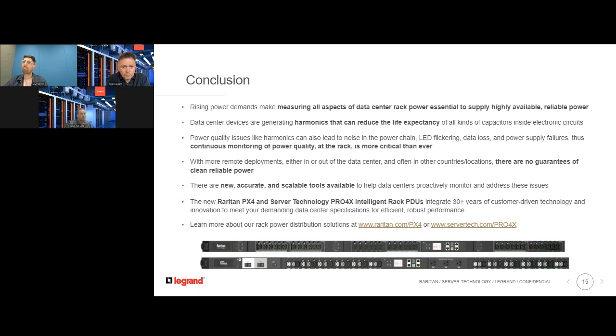Because our attendee is concerned about the impact that this could have on the network and also on the TACACS server. Yeah. So first of all, in a classical environment, you have a central DCIM software available, which nowadays constantly pulls data from all the distributed PDUs. And our PDUs would by default not send out any data on its own, right? Unless you have a DCIM software which supports modern APIs. But in such a scenario, which just got described, you usually also have a dedicated infrastructure network in place, and the PDUs are usually connected to this dedicated infrastructure network.